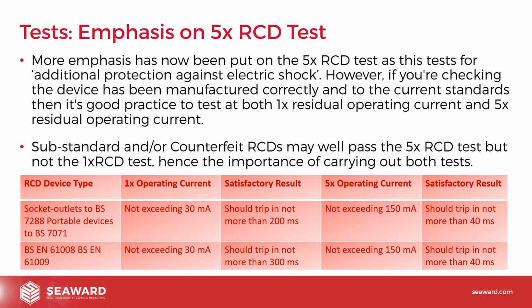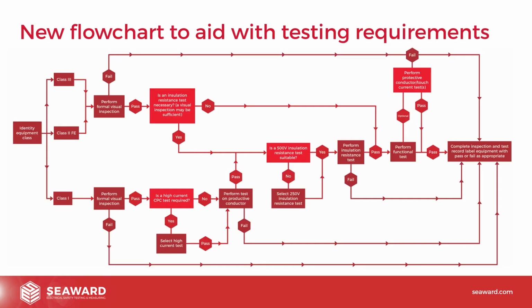But in the new code of practice, they've put in that the essential test is the 5 times test. So again, when we're talking about 5th edition compliant testers, make sure that your tester will do a 5 times RCD test when you're doing RCDs, because that's now a requirement of the 5th edition code of practice.